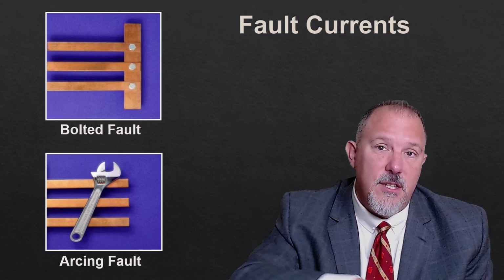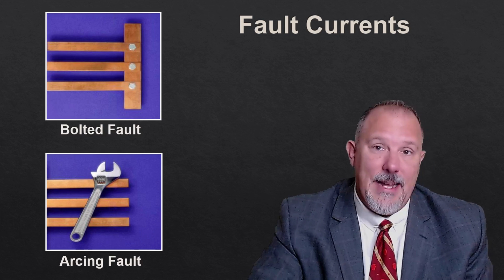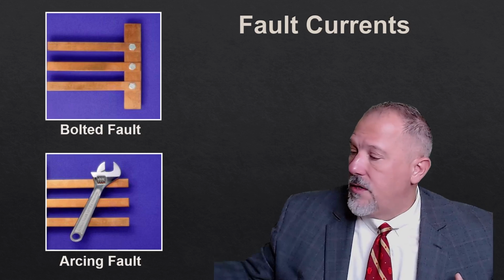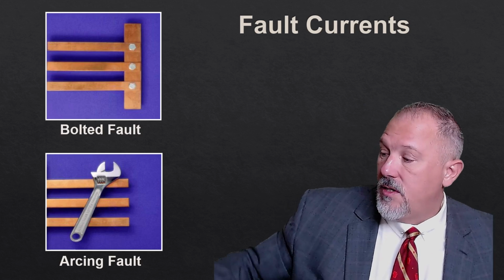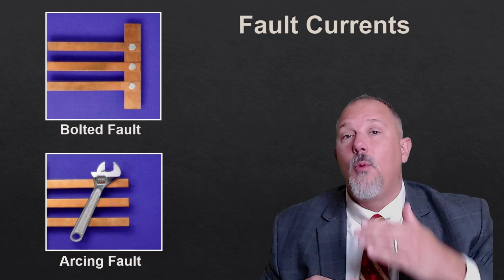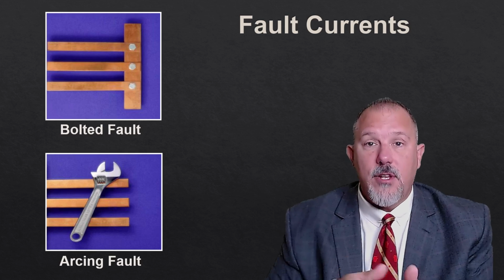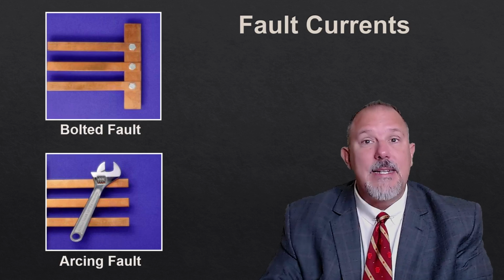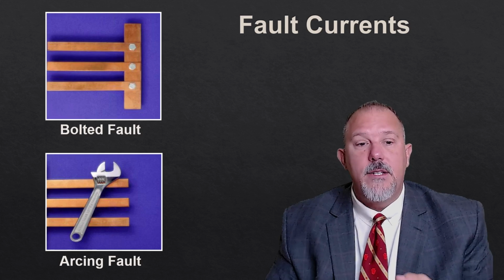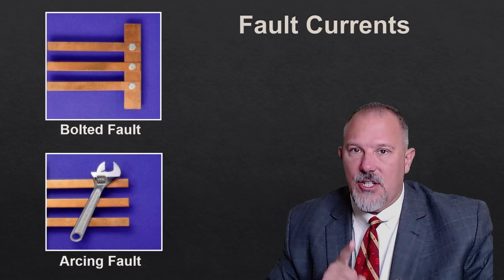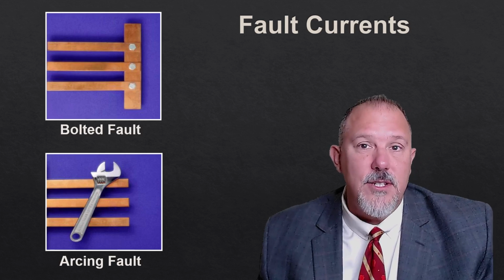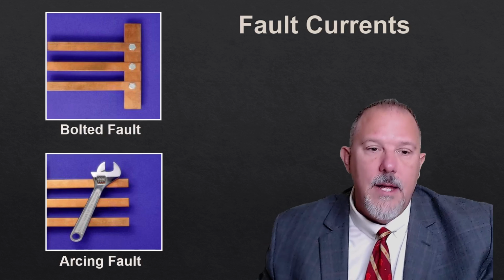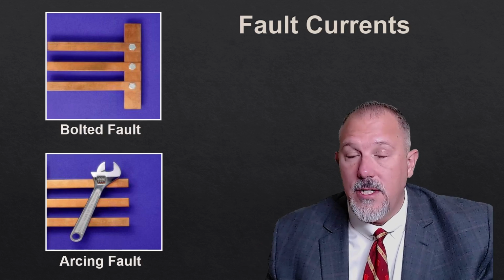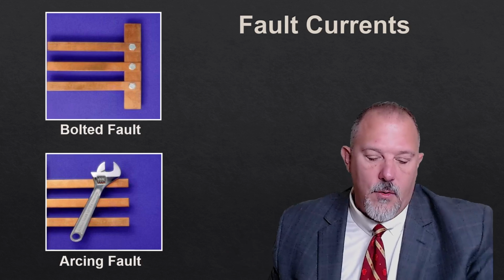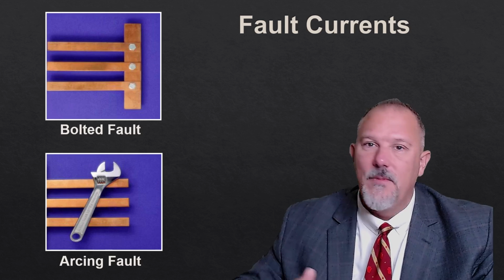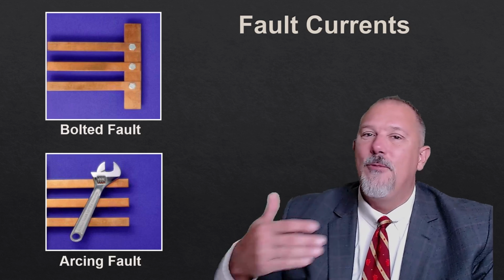That tool is based upon test data, tests over and over and over, done by the IEEE. Dr. Lee was the professor who helped develop the equations that we use today to calculate arcing currents and incident energy. And although it's not defined in the National Electrical Code, arcing current is a term that's defined in IEEE 1584, and we calculate two values of arcing current for 1584. And we get two different clearing times, and we get two different incident energy values, and we pick the largest incident energy value.